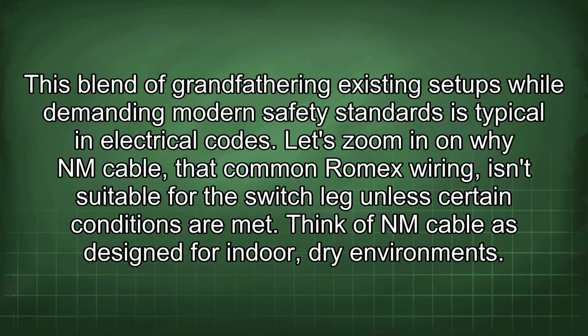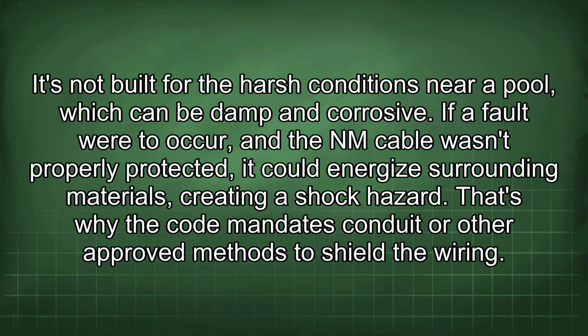Let's zoom in on why NM cable, that common Romex wiring, isn't suitable for the switch leg unless certain conditions are met. Think of NM cable as designed for indoor, dry environments. It's not built for the harsh conditions near a pool, which can be damp and corrosive. If a fault were to occur, and the NM cable wasn't properly protected, it could energize surrounding materials, creating a shock hazard. That's why the code mandates conduit or other approved methods to shield the wiring.